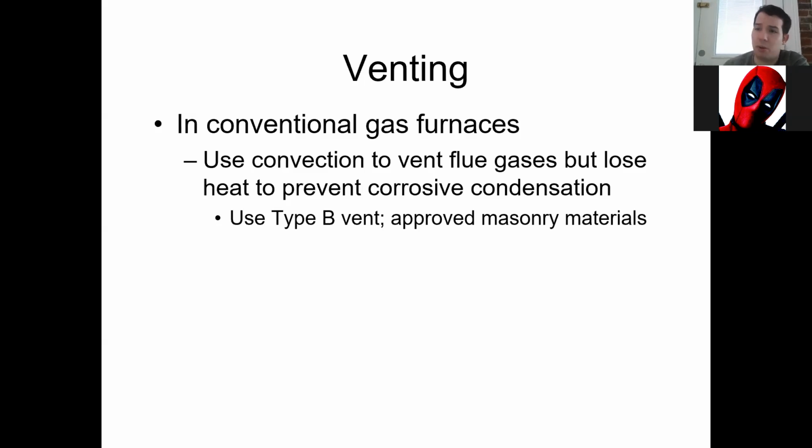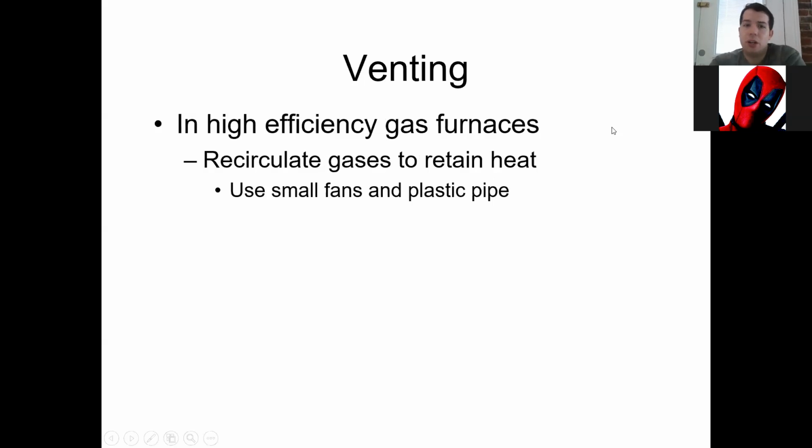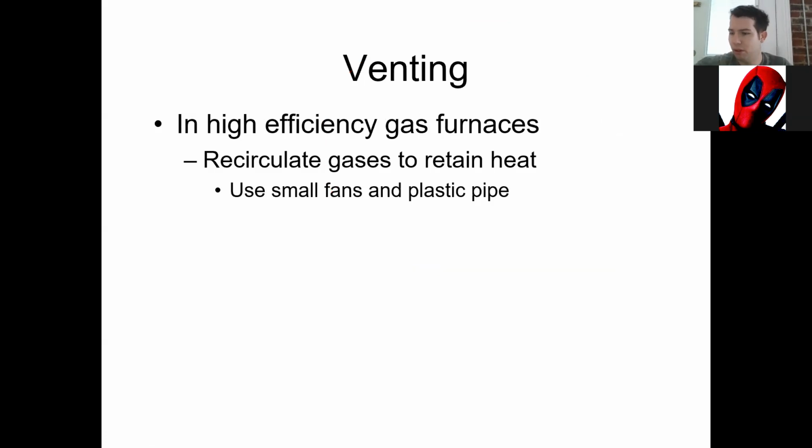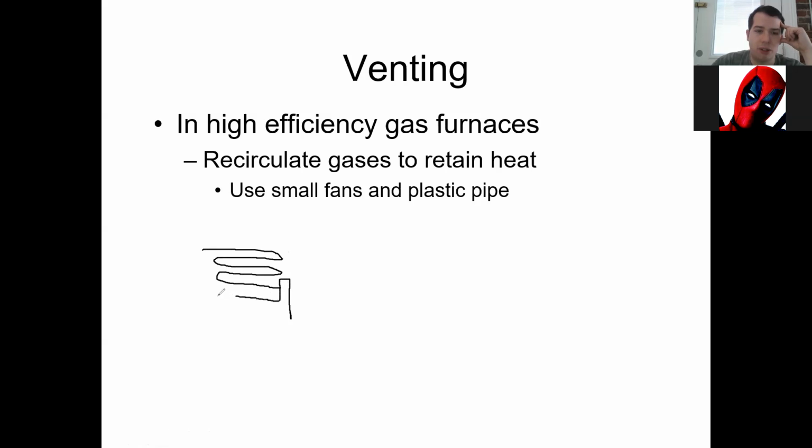Again, with flue gases, the big thing we're looking out for is condensation. It can cause a lot of issues. The high efficiency furnaces we've talked about before, because they're highly efficient, are going to have multiple stages of heat. They're going to have multiple heat exchangers, that first and second stage of heat. We've got that first stage, that big S-shaped section, and then it goes back into that one box, and then it feeds down, and you've got all those little tubes.